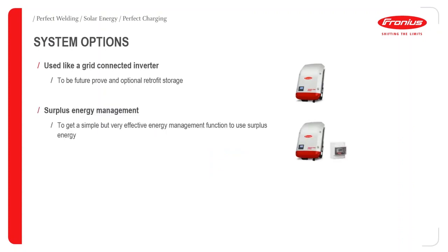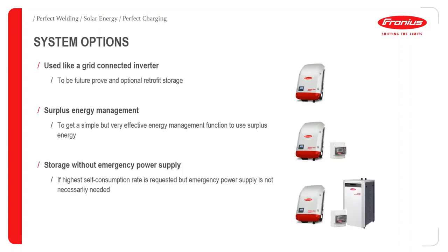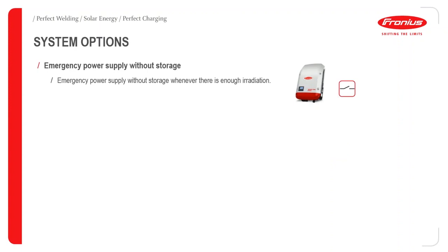So in terms of system options, the hybrid can just be installed by itself, so it can be used as a normal grid-connect inverter, just with your normal PV and no meter or battery. Then you can add the meter, sorry, and the battery at a later date if you want to do some energy management, for example turning on external loads dependent on what the site's doing if you've got excess energy. And then also have the battery in there so any excess power will be stored in the battery.